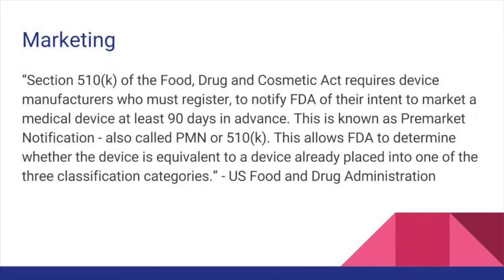Marketing. Section 510K of the Food, Drug, and Cosmetic Act requires device manufacturers who must register to notify the FDA of their intent to market a medical device at least 90 days in advance. This is known as the pre-market notification, also called PMN or 510K. This allows the FDA to determine whether the device is equivalent to a device already placed into one of the three classification categories.